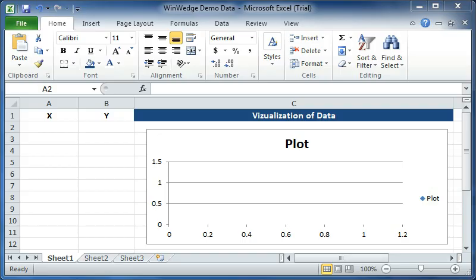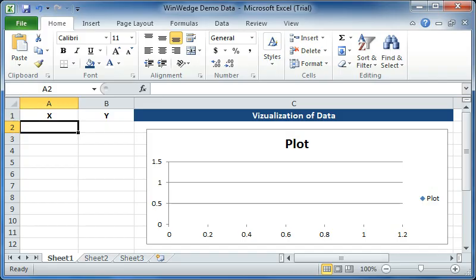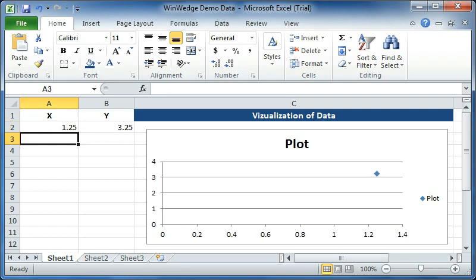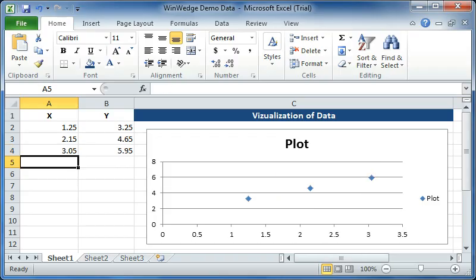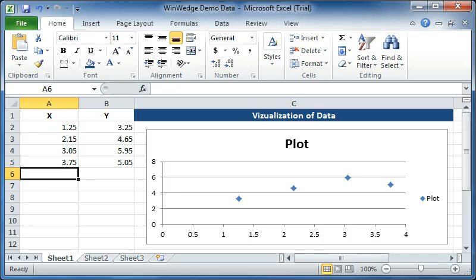When I do this, WinWedge sends the question mark out of the serial port to the instrument, which immediately returns the data containing the X and Y values. WinWedge then reads in the data, parses it into the two separate data fields, and finally types the data into Excel exactly the way I want, with the two values being sent to two columns. Each time I press the F9 hotkey, I will receive back a new set of data from the instrument. As you can see, WinWedge makes it very easy to take data from any RS-232 instrument.